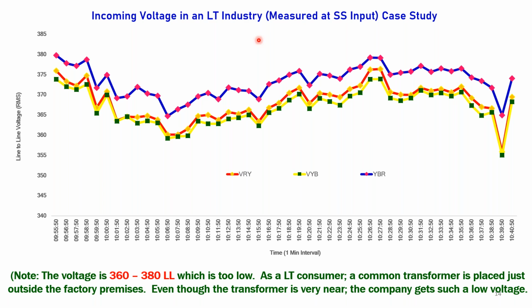So we conducted the study at the input of the transformer, and we found that the input of the transformer in the morning time is going to be around 360 to 380 line-to-line voltage. So this company experiences a huge amount of voltage fluctuation during the daytime and night time. Therefore, they installed a 200 kVA oil-cooled servo stabilizer to arrest the voltage fluctuation, to keep their voltage constant and keep their equipment under safe mode of operation.